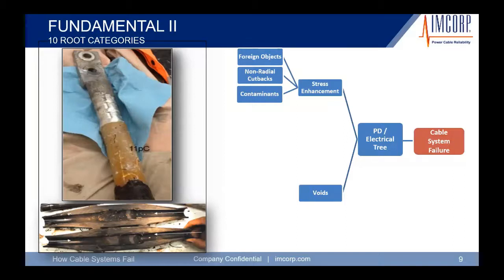If you take a look at the ring cut, and I've seen this in the field many times, these guys don't necessarily make a ring cut, they just kind of whittle away the semiconductor material. Again, a lot of sharp points, areas of stress enhancement that can eventually cause this cable termination to go to failure.